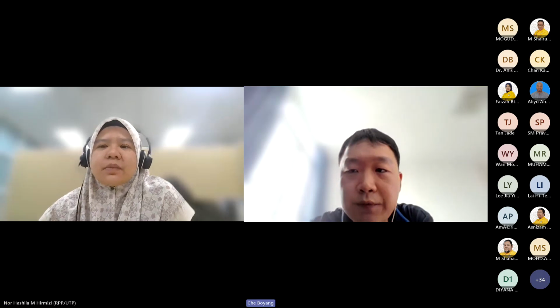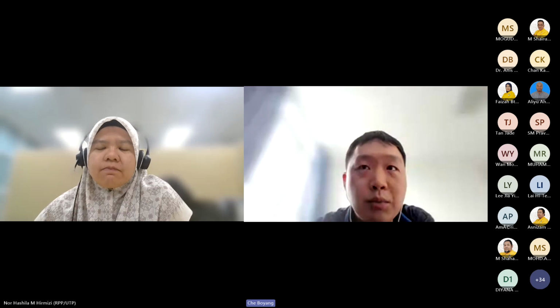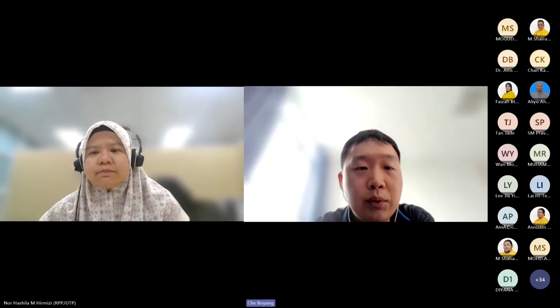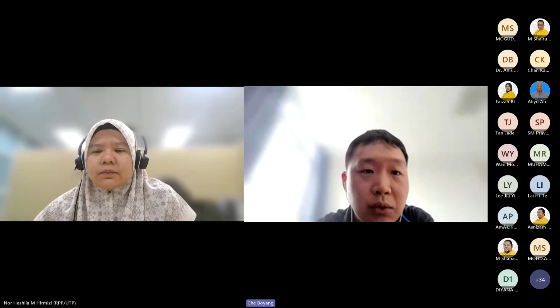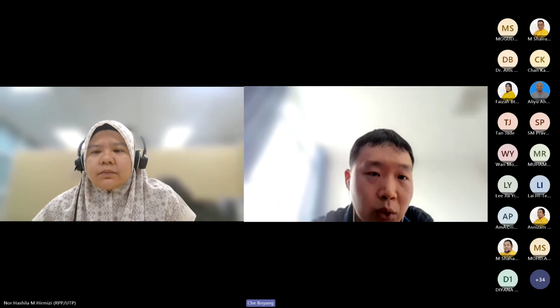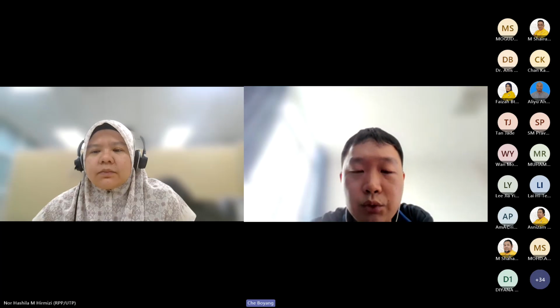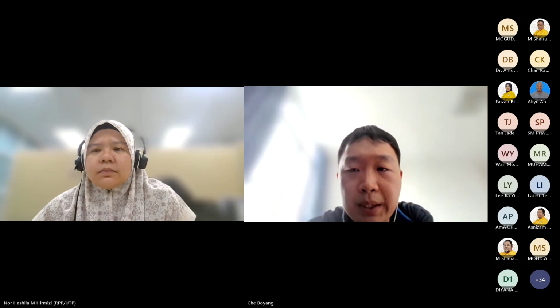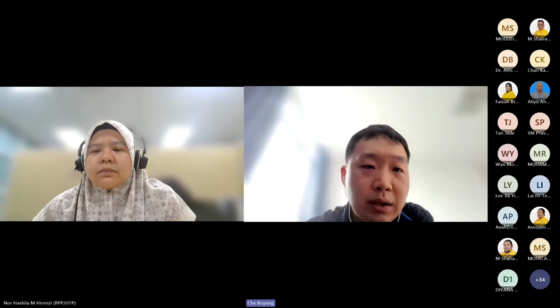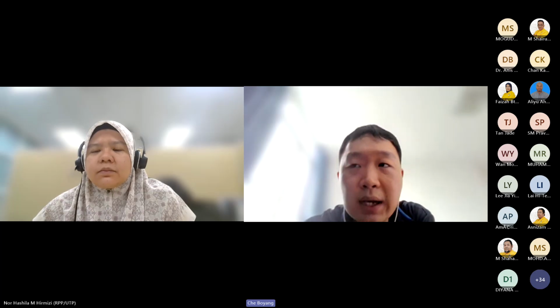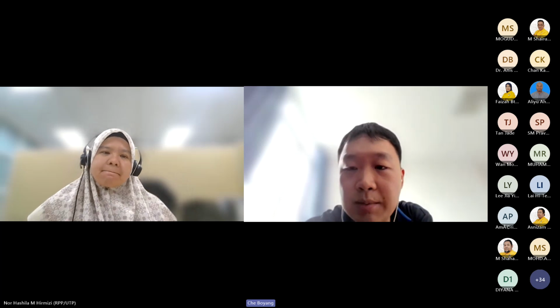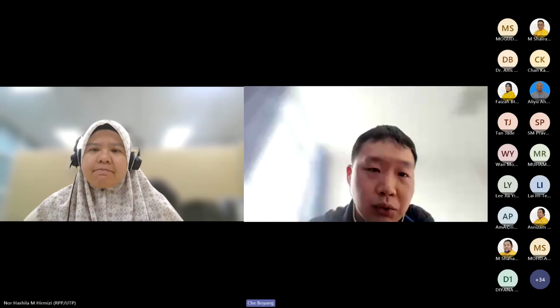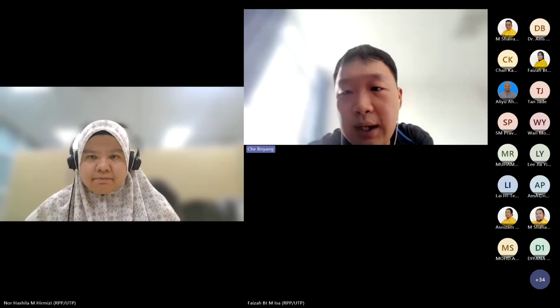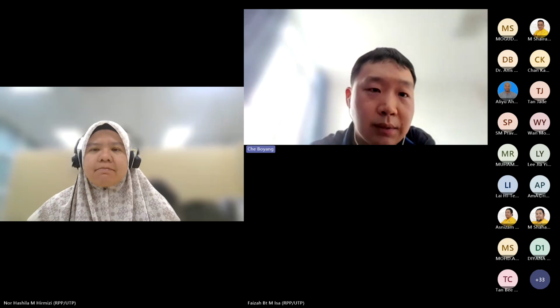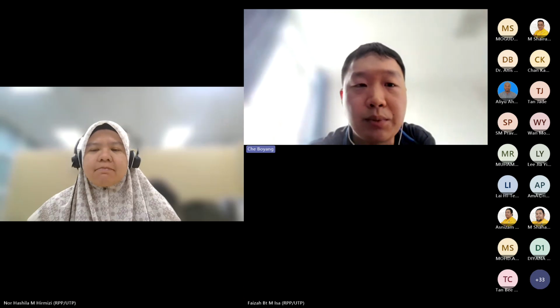For liquid, we do have an accessory, which is like a cuvette holder. You prepare your sample inside the cuvette and place it in the sample holder, and then the laser is directed to the cuvette and gives you the signal from this liquid sample. But in this case, you won't get the optical image if you measure using this liquid holder. Another way to test liquid is to drop some liquid on a glass slide and place it under your microscope objective lens. If you are able to focus on the liquid drop, then you will be able to get your liquid sample signal.